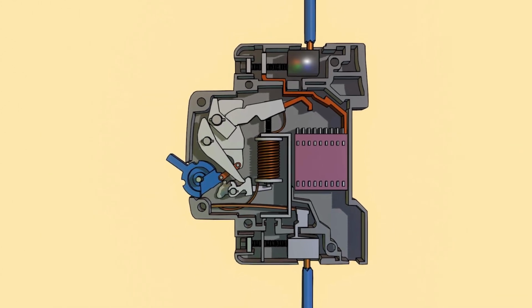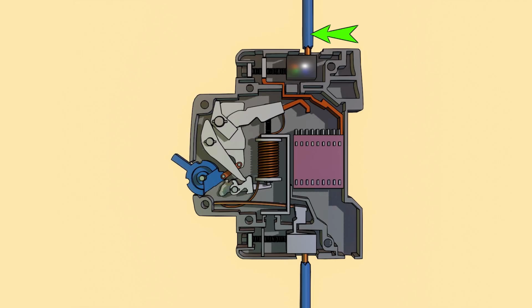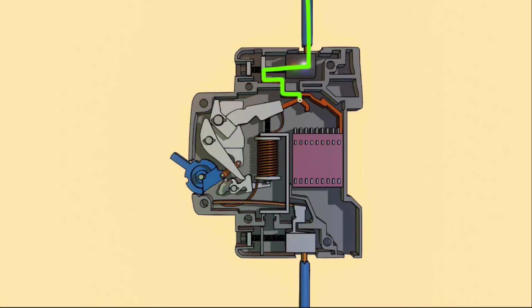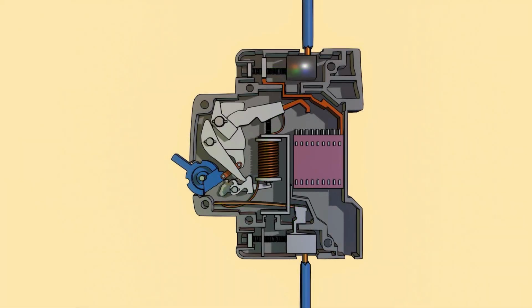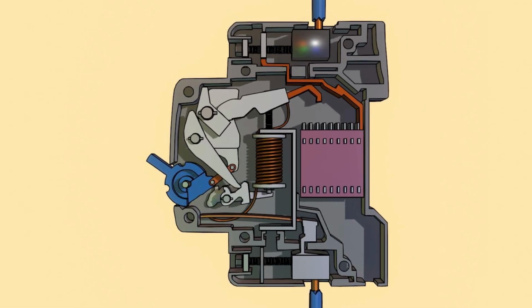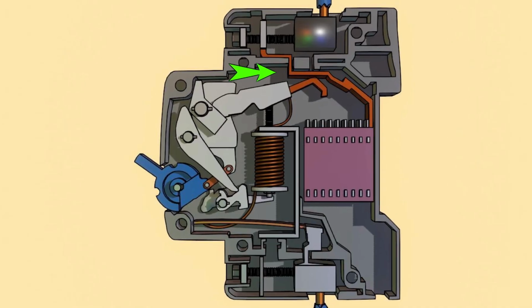Now let us explain with the image. This is the external connection of one side. This is the external connection of the other side. During switch on condition, current starts flowing through this part. This is the fixed contact, and this is the moving contact. From this connection, current flows to the coil. Then from this coil, it flows through the bimetallic strip and finally comes out from the external terminal.